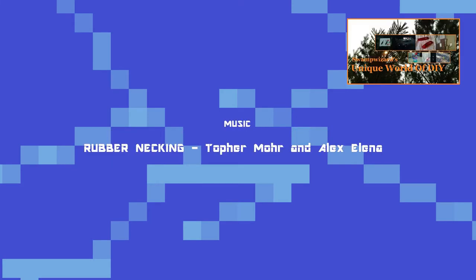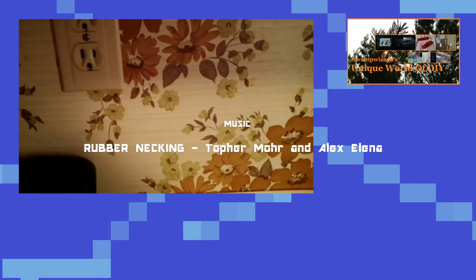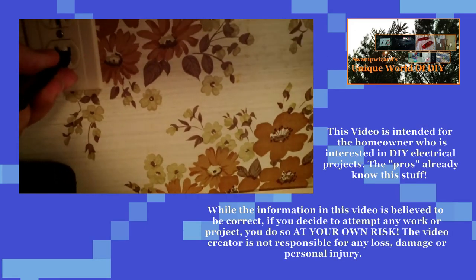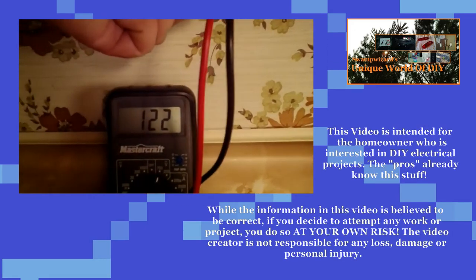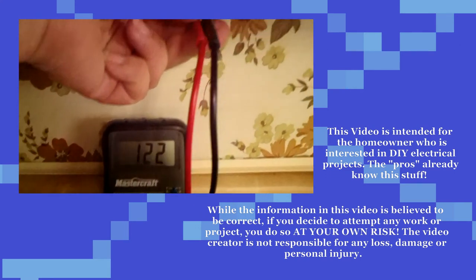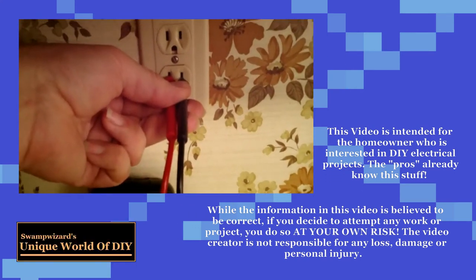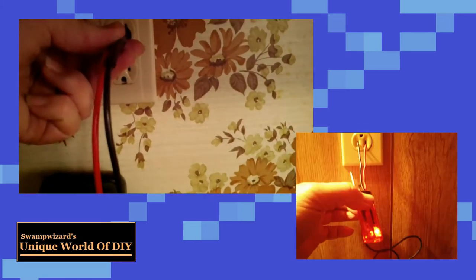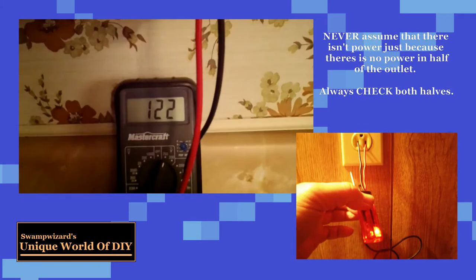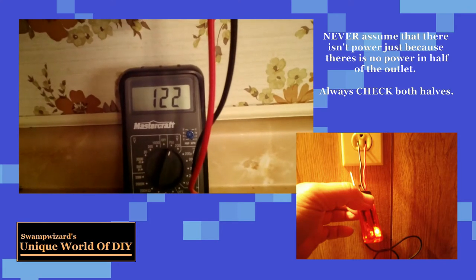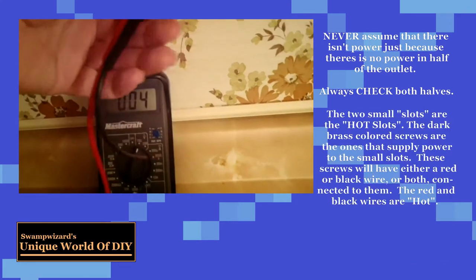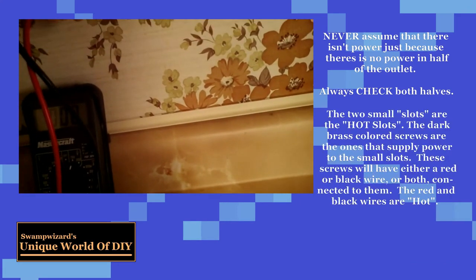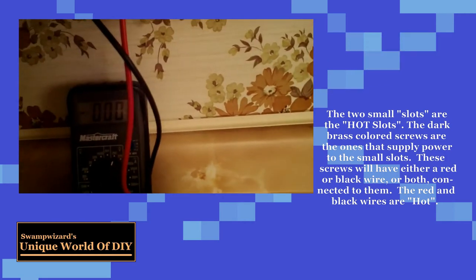Hey there, everybody. I was doing some electrical work the other day, and it got me thinking that if you have to remove an outlet, here's something that you may want to check. Some outlets are split, and that is that they get power from both sides of the 240-volt supply. If you just put your test light or your voltage probes into the upper half of the outlet or the bottom half of the outlet, there may actually be power in there even after you turn off the breaker. You could get a real nasty surprise that way.